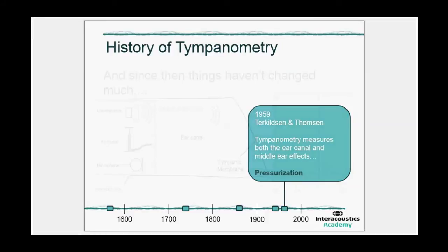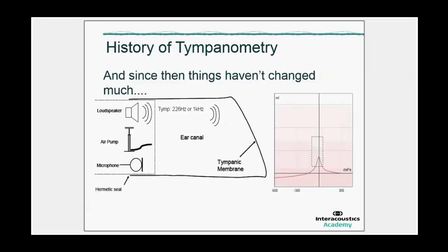So pressurization was added back then. And if you look at the tympanometer of that day, then the tympanometer did not change anymore between then and today. If you imagine what you see on the screen here is an ear canal in which we inserted a probe. The probe has a speaker to make a probe tone, which is typically 226 hertz, or for babies it is 1000 hertz. It has a pump so we can pressurize the ear canal, and it has a microphone to measure the response. This really didn't change much for the last roughly 50 years.